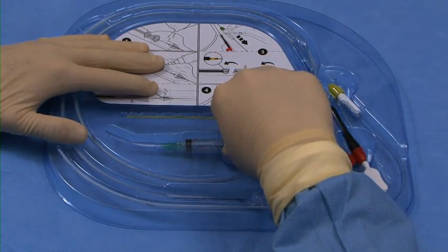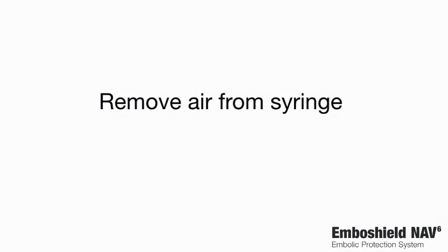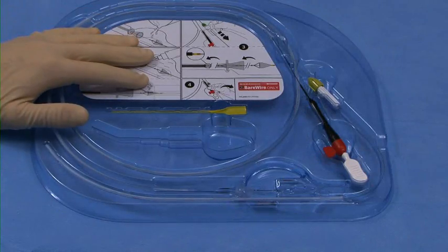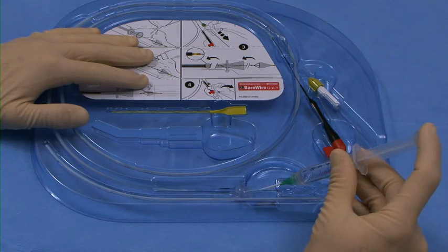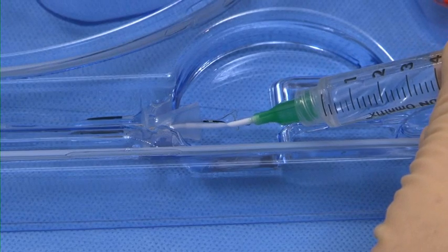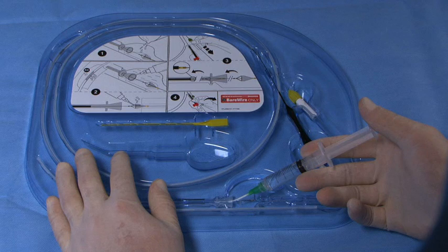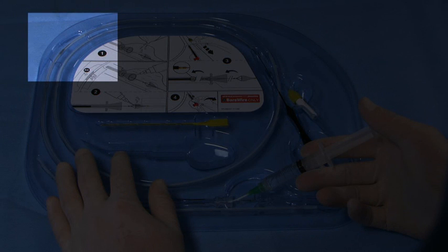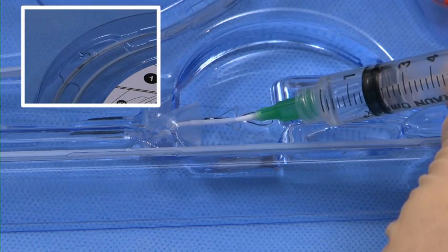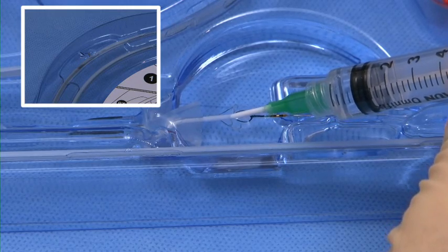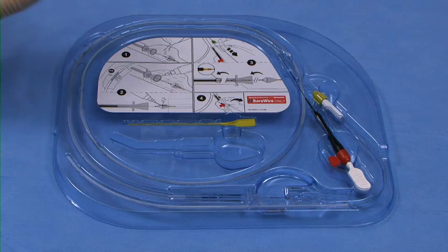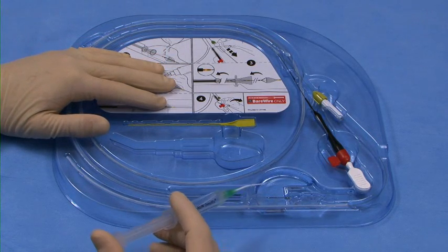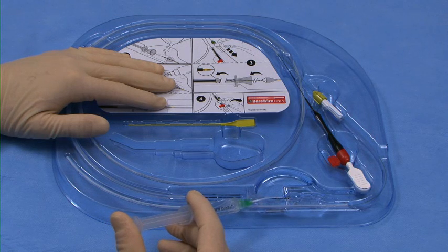Fill the provided syringe with heparinized normal saline. Remove air from syringe. To flush the delivery catheter, push the white flushing tip into the core of the loading funnel until it engages the internal diameter of the funnel. Flush the catheter lumen until heparinized normal saline can be seen exiting at the rapid exchange exit port. To remove any air bubbles from the filtration element, place the white flushing tip gently inside the filtration element and flush until all air bubbles are removed.